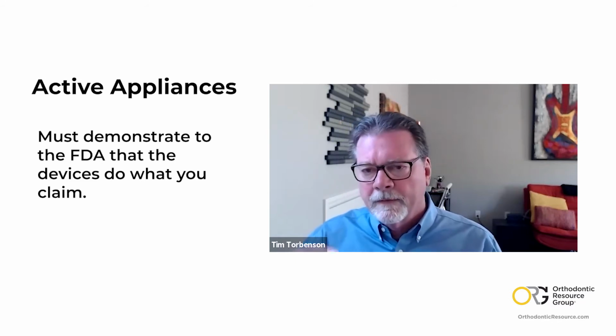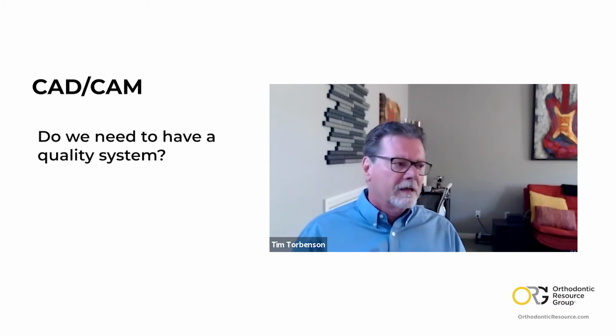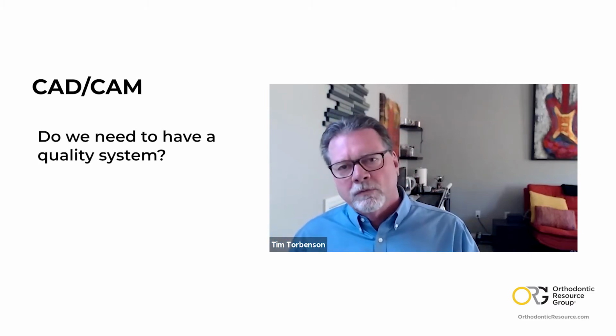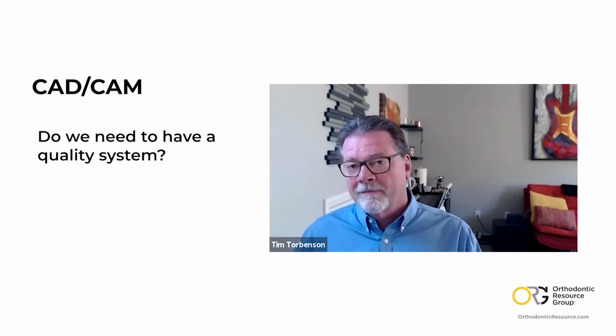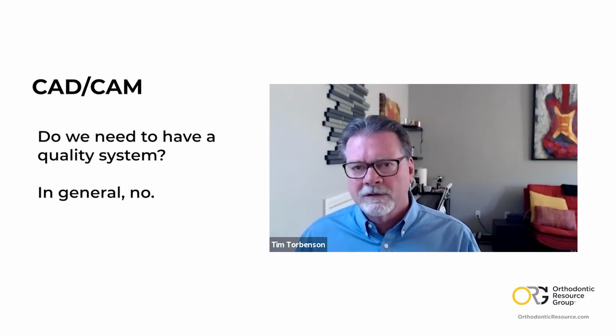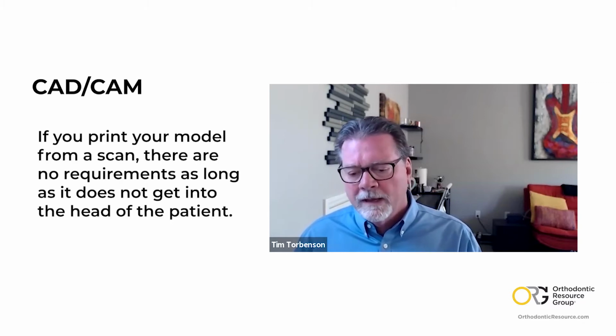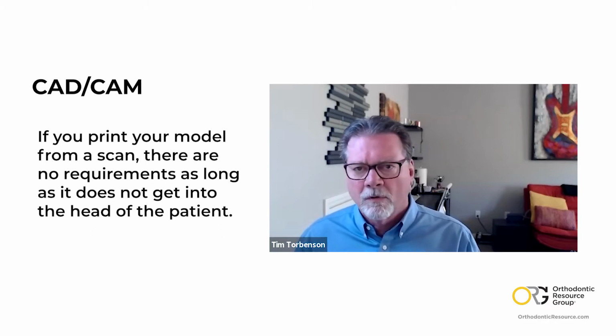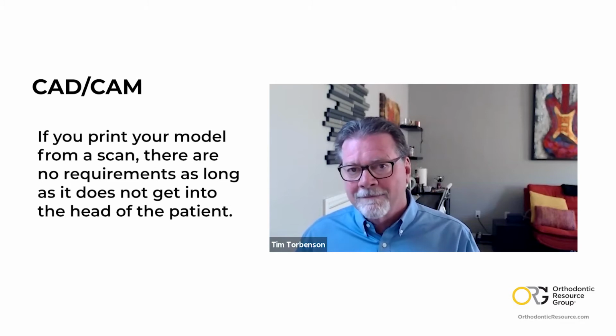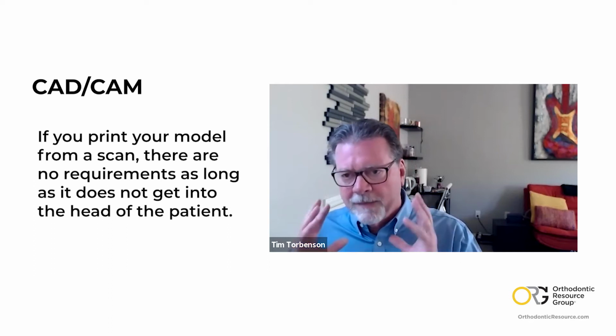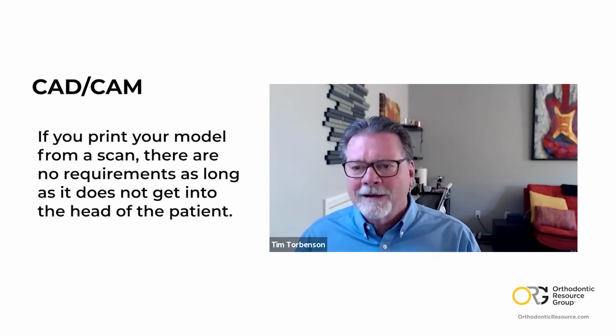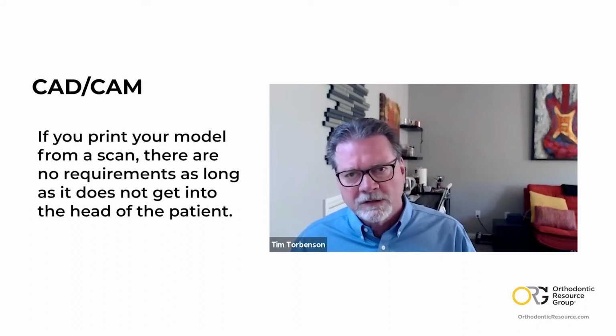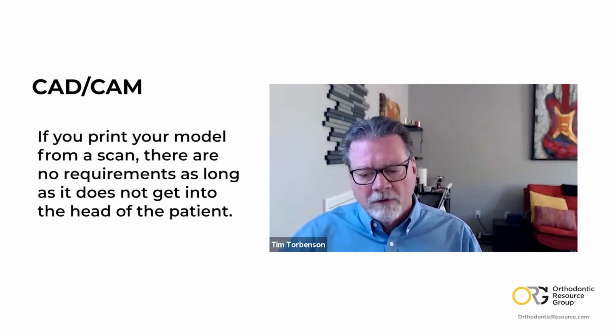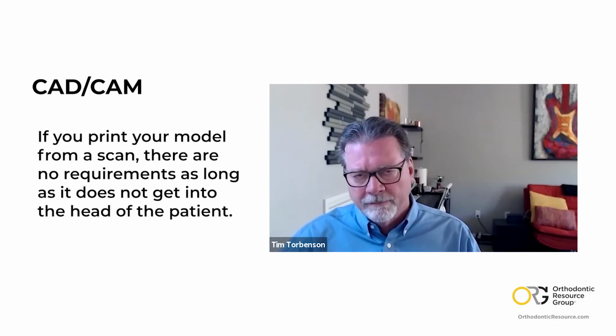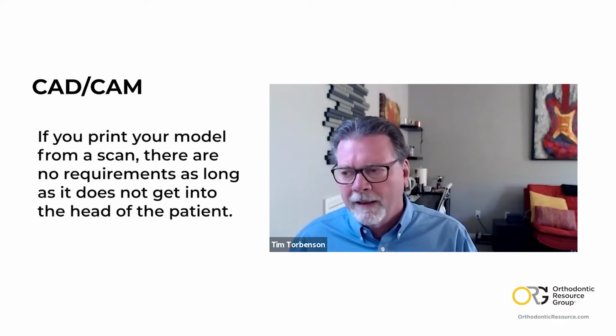Very few. And let me go back to the CAD/CAM issue, because you had mentioned, if we get into the CAD/CAM process, does that mean that we have to have a quality system? And the answer to that in general is no. If you are scanning your impressions, or you receive an intraoral scan, and from that you print your models, because that model never gets into the patient's head, it's not permanently implanted, or it's not an appliance itself that goes into the patient's head, then there are no quality requirements for that process of printing a model.